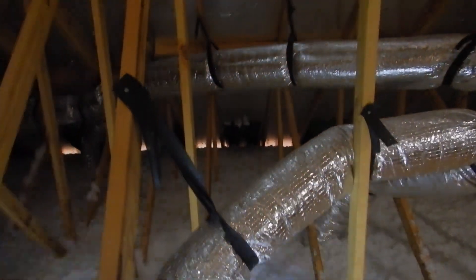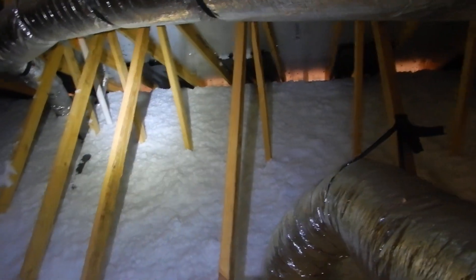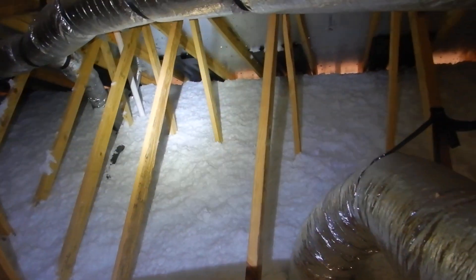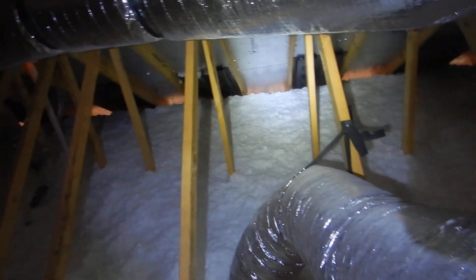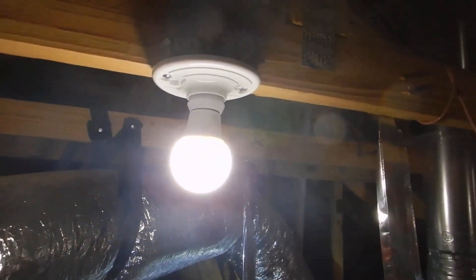Let's move through here a little bit. Missing baffles — look at all that daylight. Missing baffles, missing baffles. When you have continuous soffit vents, you're supposed to have continuous soffit vent baffles. We don't have that. This attic's pretty hot — it's 110 outside. Our luminaires over there do not have protective cages on them.